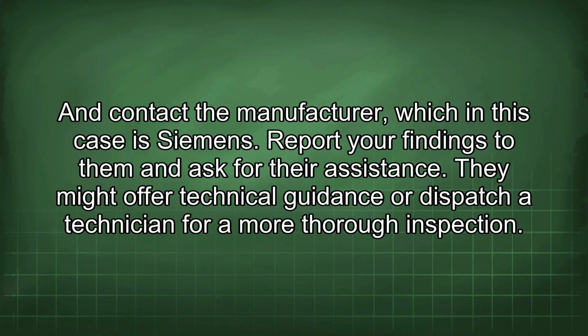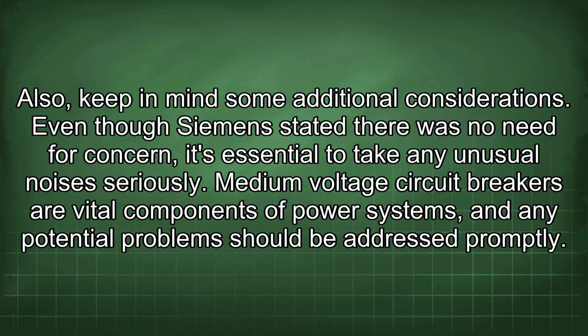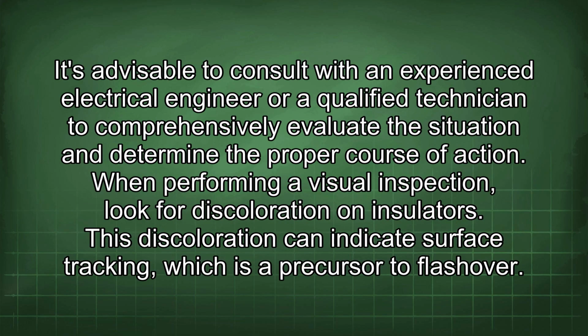And contact the manufacturer, which in this case is Siemens. Report your findings to them and ask for their assistance. They might offer technical guidance or dispatch a technician for a more thorough inspection. Also, keep in mind some additional considerations. Even though Siemens stated there was no need for concern, it's essential to take any unusual noises seriously. Medium voltage circuit breakers are vital components of power systems, and any potential problems should be addressed promptly. It's advisable to consult with an experienced electrical engineer or a qualified technician to comprehensively evaluate the situation and determine the proper course of action.